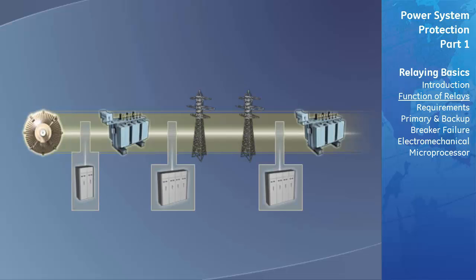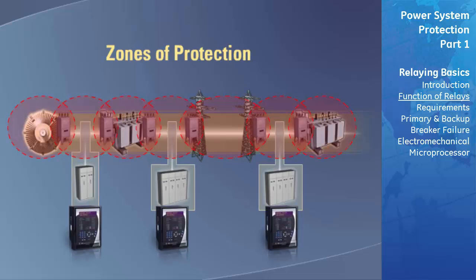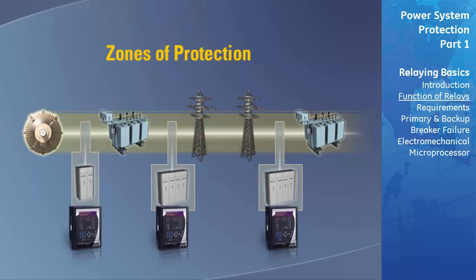One of the protection engineer's most powerful tools is the concept of zones of protection. The boundary of a protective zone represents the region that a particular protective element covers. It is necessary for these zones to overlap to ensure proper protection. If two zones did not overlap and a fault occurred at the boundaries of these zones, it is possible that no relays would be tripped.